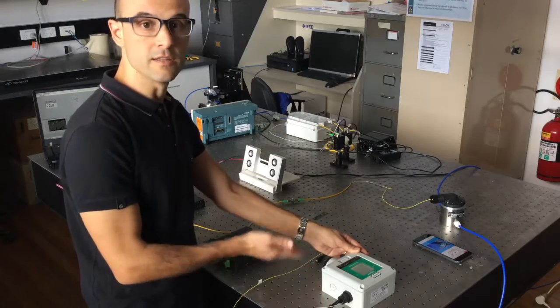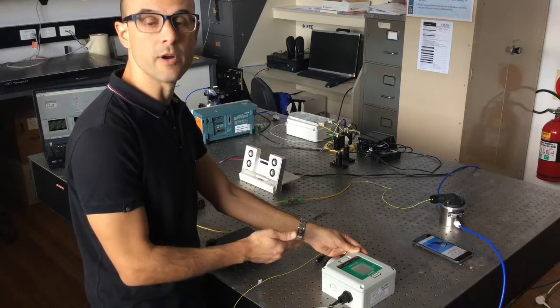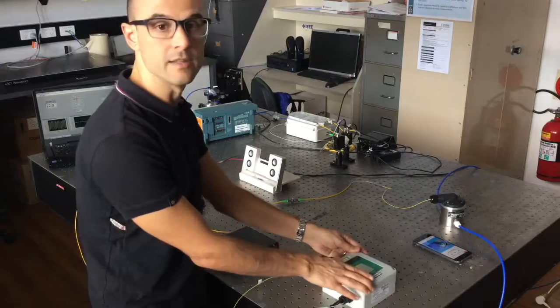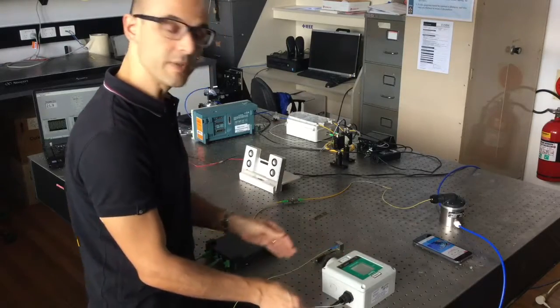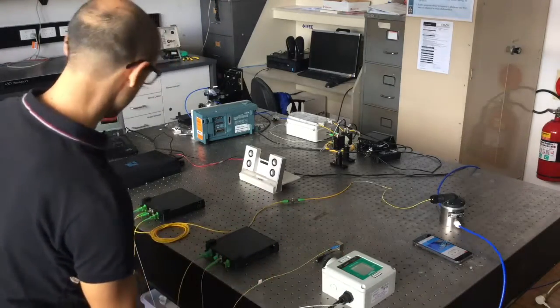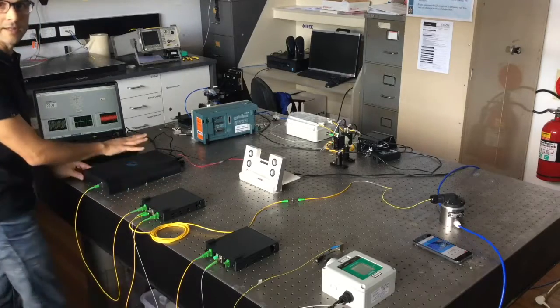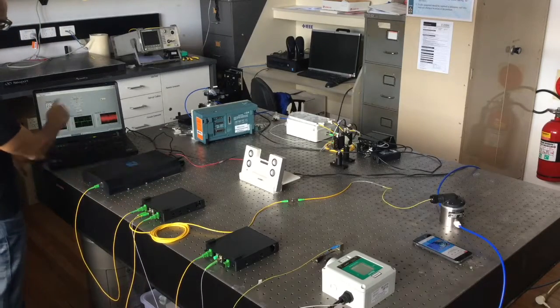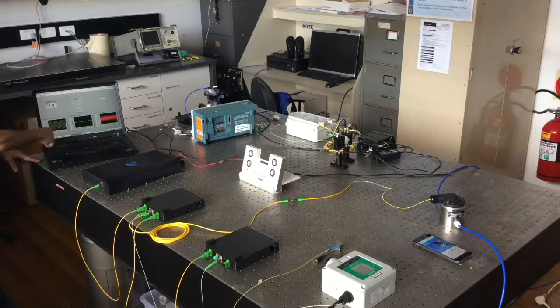And then this signal, the square wave, is applied to one of our optical transducers that's inside this box. And the optical signal is then read at this end here, and it's shown in the display. So this is the signal that we read optically from the gas sensor, and this is the corresponding reading once the frequency is converted back into the oxygen percentage.